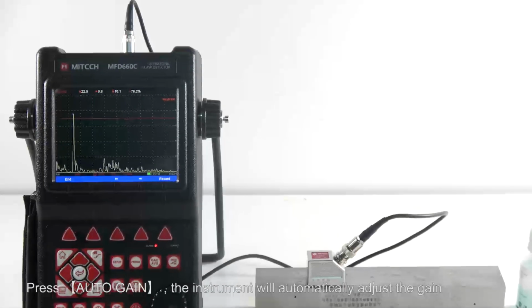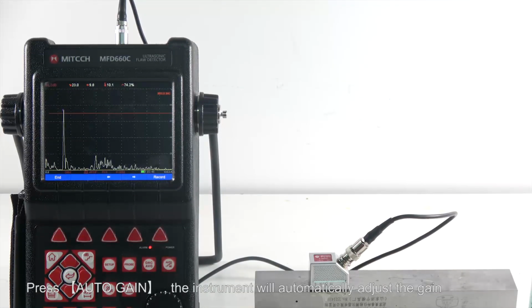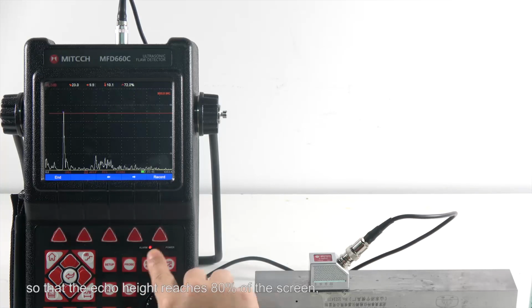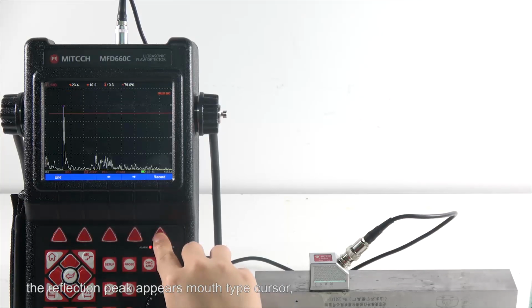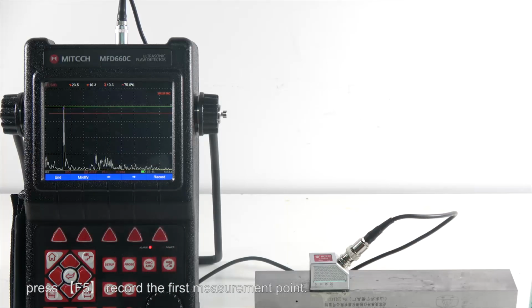Press auto gain. The instrument will automatically adjust the gain so that the echo height reaches 80% of the screen. The reflection peak appears with a cursor. Press F5 to record the first measurement point.